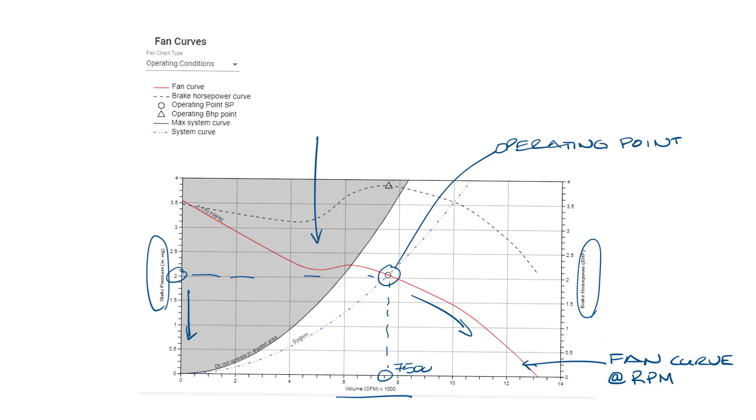You can see this dip over here at about two and a quarter inches of static pressure where you actually have two different CFMs. Somewhere around 4500 and about 5700 CFM. So which one would it operate at? Well, the fan is going to hunt between these two air flows at this point.